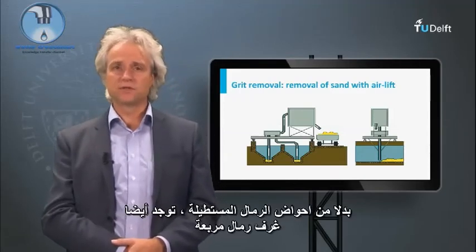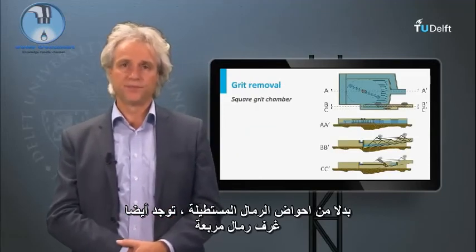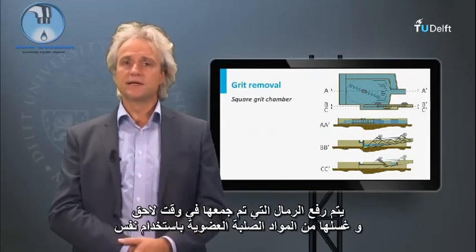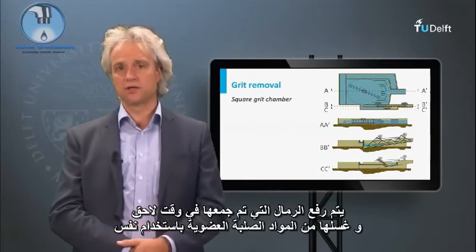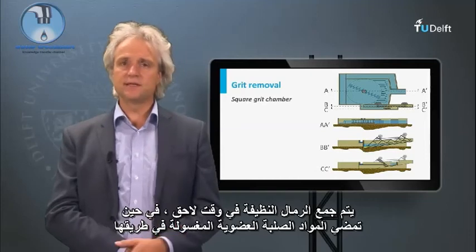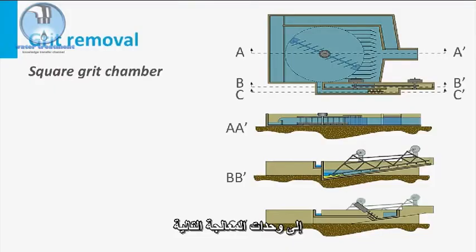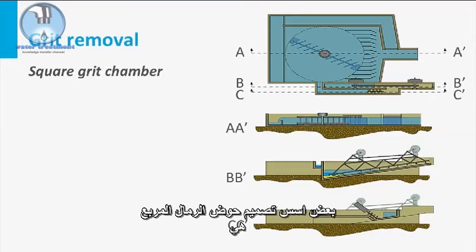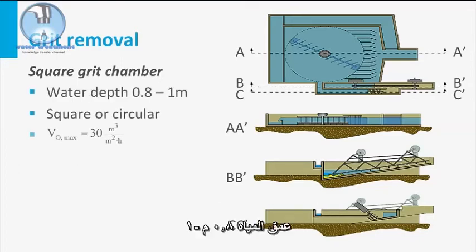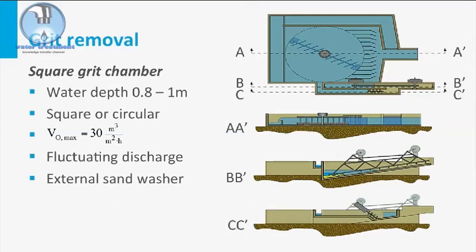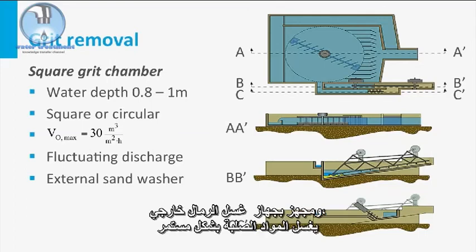Instead of rectangular grit chambers, square grit chambers are also applied. In this design, the sand is moved to one lateral side by a slowly moving hopper. The collected sand is subsequently lifted and washed from organic solids using the incoming flow. Clean sand is collected, whereas the washed organic solids proceed to the next process units. Some design features of a square grit chamber: water depth is 0.8 to 1 meter; tanks can be square or circular; maximum hydraulic surface load is 30 cubic meters per square meter per hour; the tank has a fluctuating discharge and is equipped with an external sand washer continuously washing the solids.